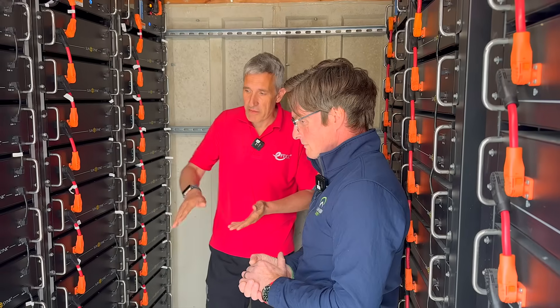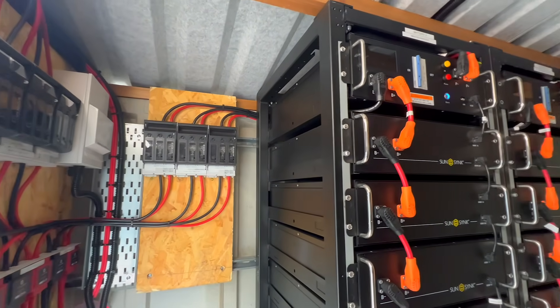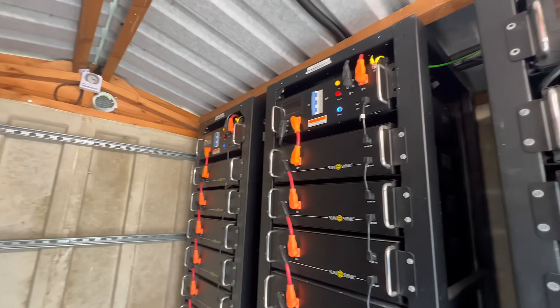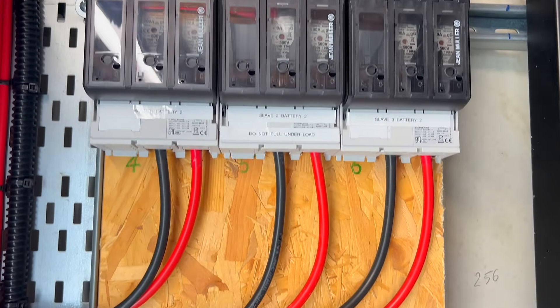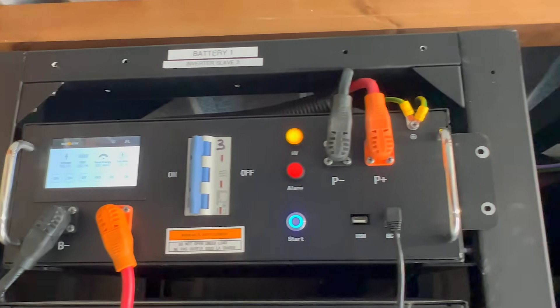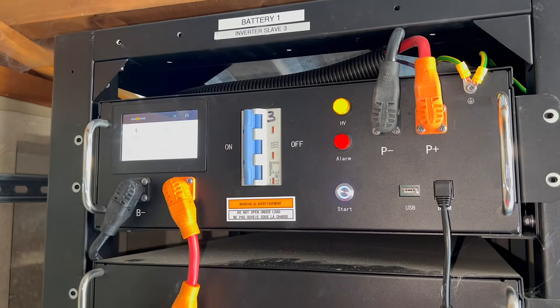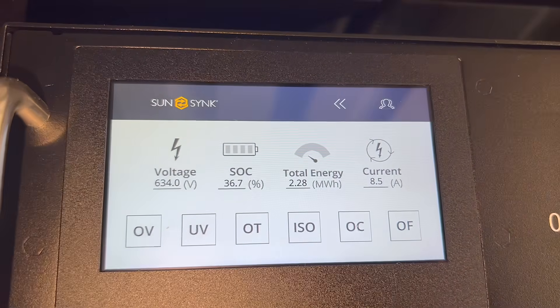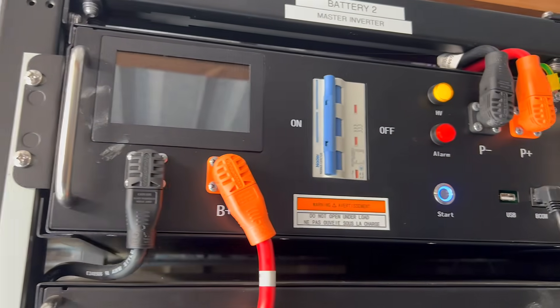The individual batteries are 51-volt DC units running in series, adding up to 600 volts. That high voltage keeps the size of the cabling back to the inverter down. The box at the top of each unit is the battery management unit, which controls what the batteries are doing from the inverter side. It also monitors the batteries temperature-wise and makes sure they are all balanced correctly — a slight undervoltage or imbalance can cause issues, but the BMU maintains everything as it should.